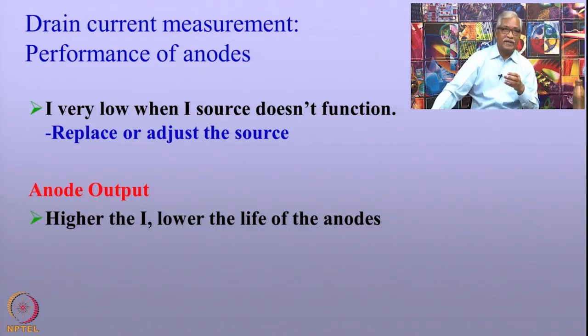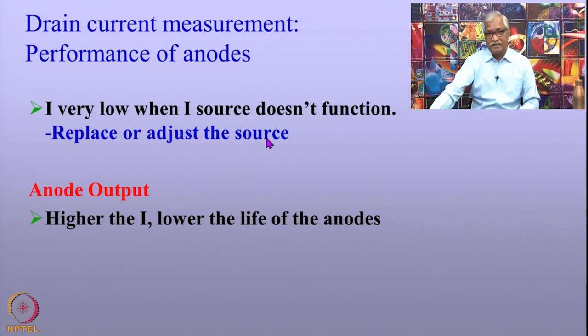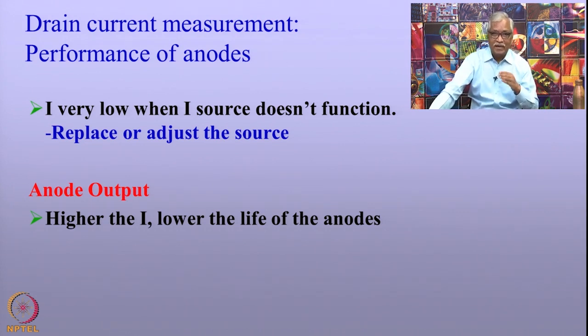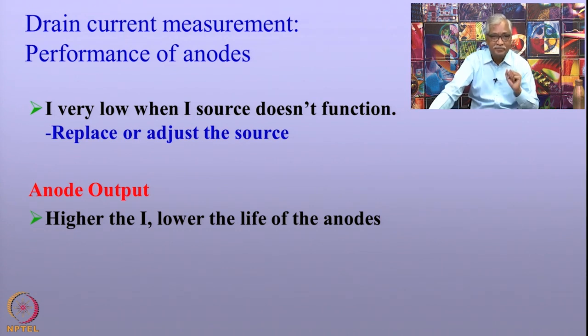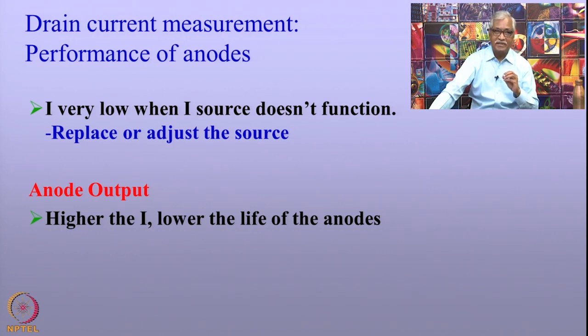Let me move on to the next technique: the drain current measurement technique. This technique is primarily used to determine the performance of the anodes. The anodes are the source of current; they disperse current into the soil, and from the anode the current goes into the soil and through the soil enters the pipeline, achieving cathodic protection. The current flowing from the anode to the pipeline is called the drain current.